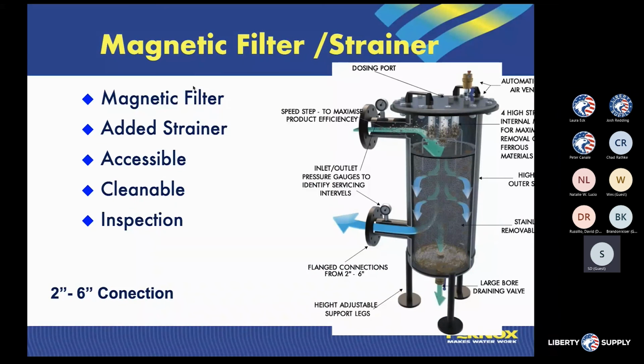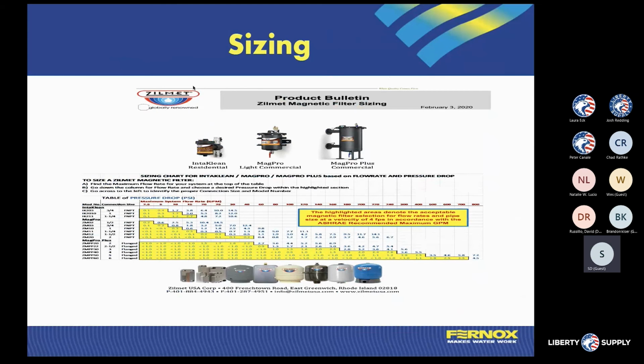In the larger series, obviously that's more of a floor mount, getting into bigger flanges, more magnetism. So this has multiple magnets in there. Depending on the size, it has 4 or 6 magnets sitting inside of the solution, but again, they're concealed in those tubes, as you saw in the video. For sizing of this type of product, we've created a nice chart so that you can look at the different size systems, look at your system volume or the flow rate through your system, and pick out what size magnetic filter would be most appropriate.